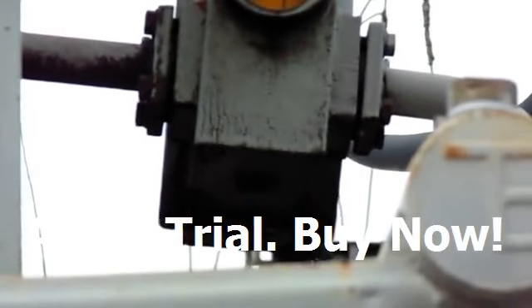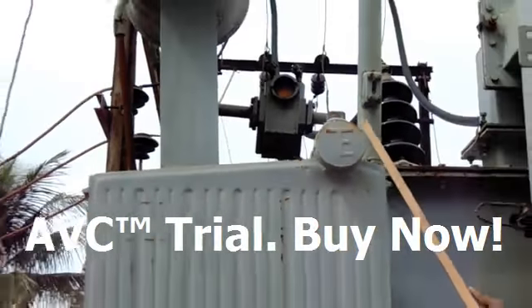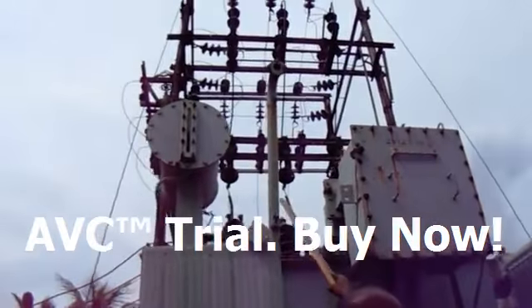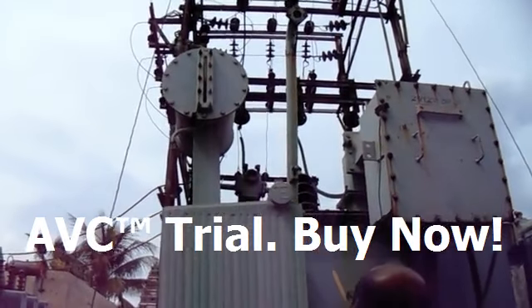Inside there are 2 mercury switches, and when the oil goes down, first it gives a warning to the operator who is sitting in the panel room. If the operator doesn't take care of that warning signal, there is another switch. When there is further heating up and the oil goes down further, the second mercury switch acts, and it isolates the transformer from the HT supply.